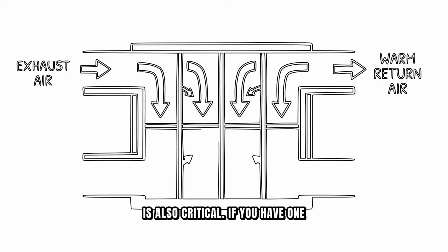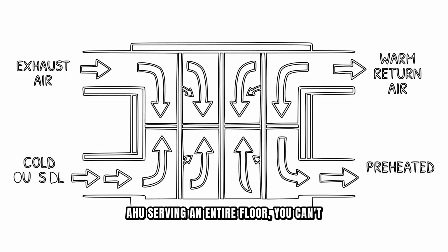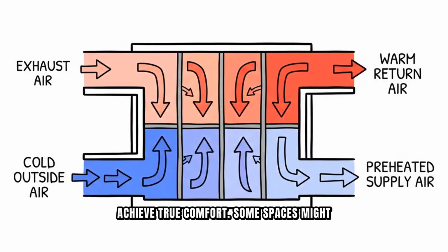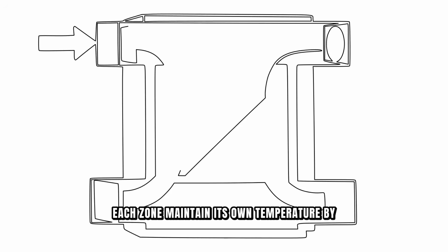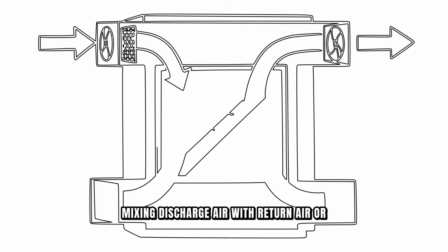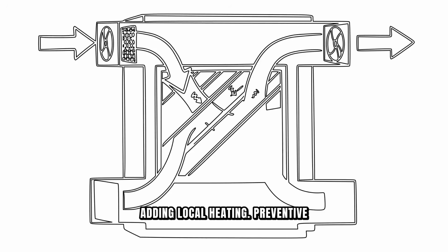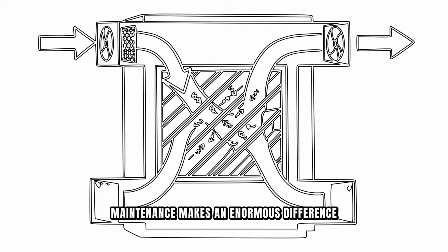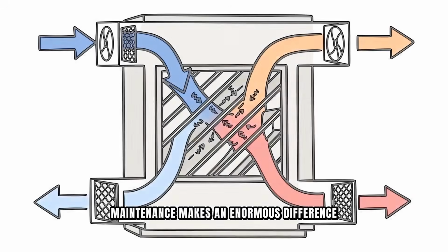Zone control is also critical. If you have one AHU serving an entire floor, you can't achieve true comfort. Some spaces might get afternoon sun and need cooling, while others stay cold. Modern systems use terminal reheat, or parallel fan-powered boxes that let each zone maintain its own temperature by mixing discharge air with return air or adding local heating.